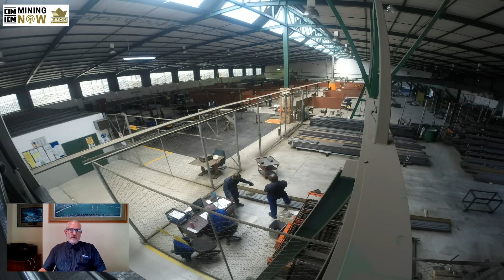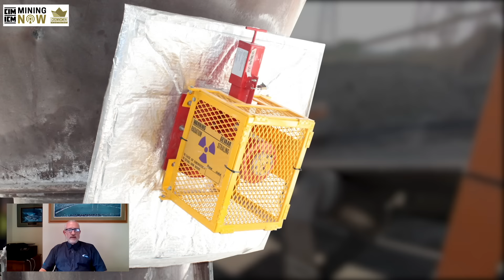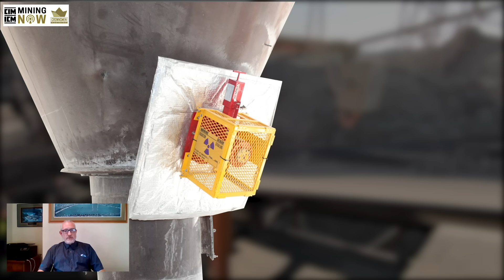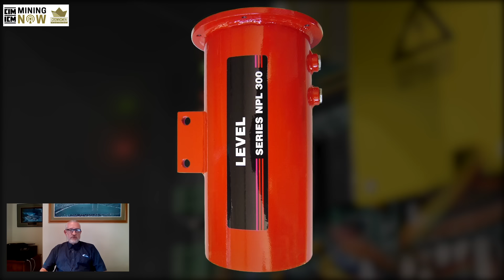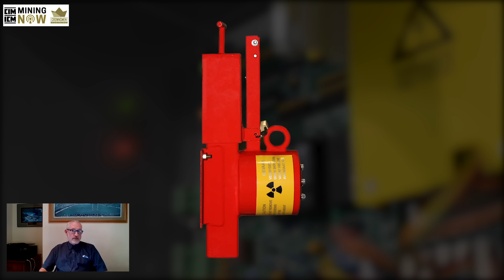But sometimes you've got real tough blockages. For instance, in the cement industry, if one of your cyclones blocks, this is at 600 degrees, you can't see inside there, and no other technology can work there. We developed a water-cooled system to measure a blockage in the cyclones in the cement industry, because they have to preheat the product before putting it into the kiln. If that blocks, it's a huge problem, because they have to wait days for it to cool down before they can clear it. So they need technology to see a tendency toward blocking and take corrective action before it becomes a crisis.